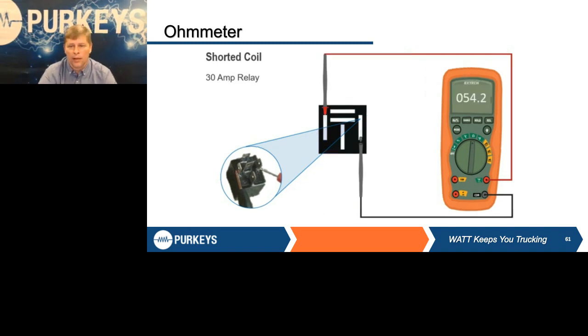Next thing we're going to check here is we got one with a much lower resistance than it should have. Now, we said before it should be between 100 and 105. This one's only at 54. So what does that immediately tell you is wrong with that coil? Somewhere in those 400 loops of wire, we have 2 loops that are touching. That's the only way that would happen. And does it matter where? No, but since we basically have half the resistance that we should, that pretty well tells you in that 400 loops of wire, somewhere around loop 200 is where they are touching. So you're only going through half as much wire as you should.